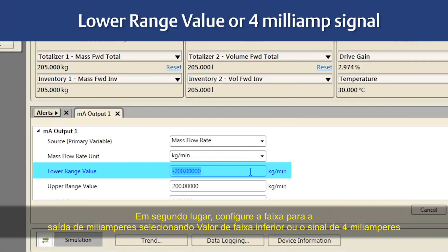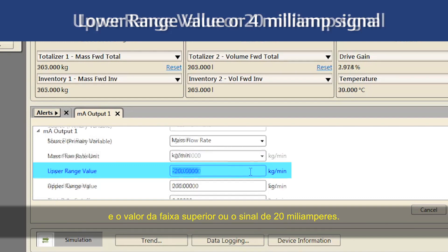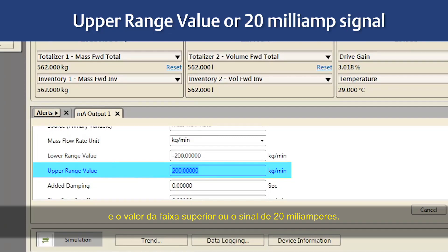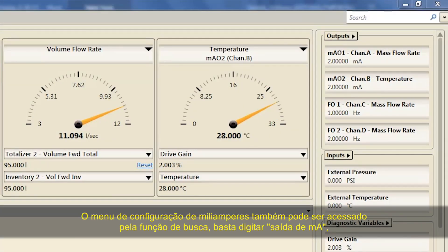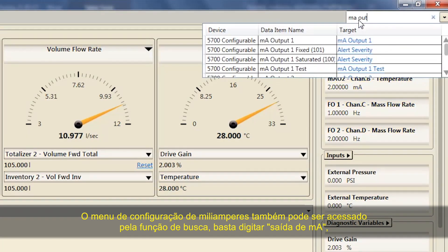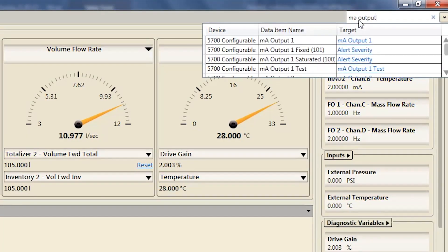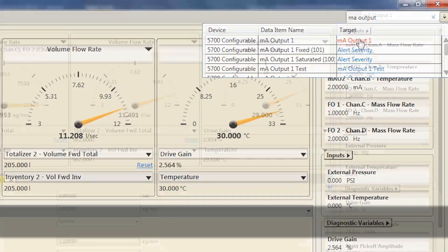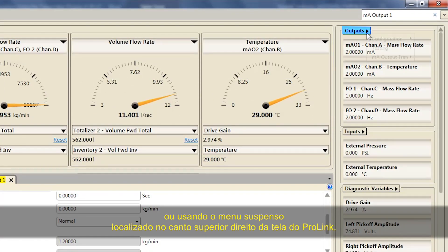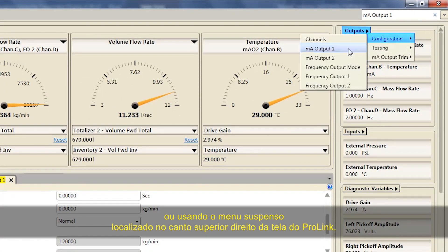Second, configure the range for the milliamp output by selecting Lower Range Value (the 4 milliamp signal) and Upper Range Value (the 20 milliamp signal). The milliamp configuration menu can also be accessed by using the search function by typing in MA Output, or using the Outputs pull-down menu located at the top right of the ProLink screen.